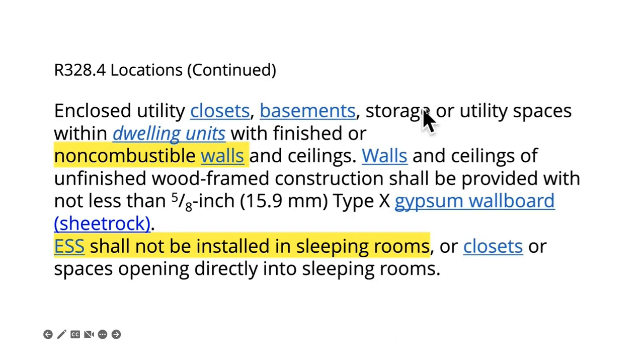Enclosed utility closets, basement, storage, or utility spaces within dwelling units with finished or non-combustible walls and ceilings. And then it also says walls and ceilings of unfinished wood frame construction. So if it's wood, then you have to make it less combustible with sheetrock, which is gypsum. And they give us the 5/8 inch gypsum. Energy storage systems are not installed in sleeping rooms or closets that open into your sleeping room.